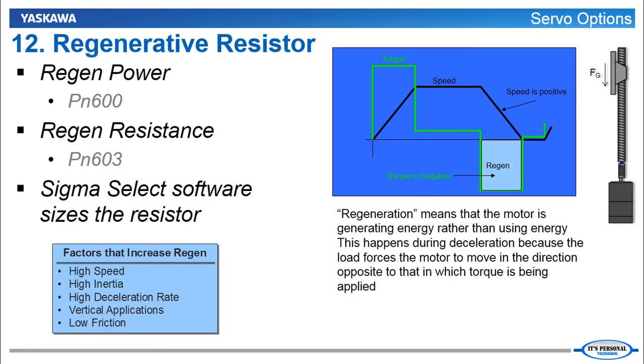Let's move on to regenerative resistor configuration. This will be important again for vertical loads. And regeneration means that the motor is generating energy rather than using energy. This happens during deceleration when you're stopping. Because the load can force the motor to move in the direction opposite to that in which torque is being applied. Consider this speed diagram. And that this vertical load would be moving downward and then stopping. So we have here the speed it goes to a certain speed and then decelerates. During that deceleration it's going downhill if you would. And that negative torque while the motor is moving forward produces what we call regeneration or just regen for short.